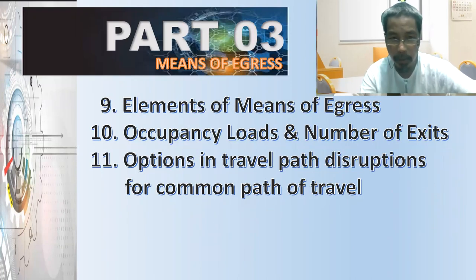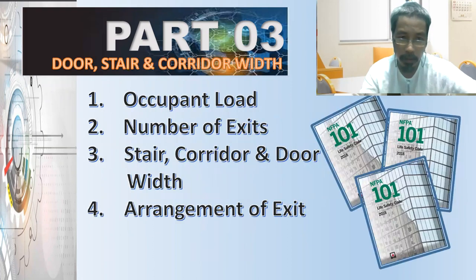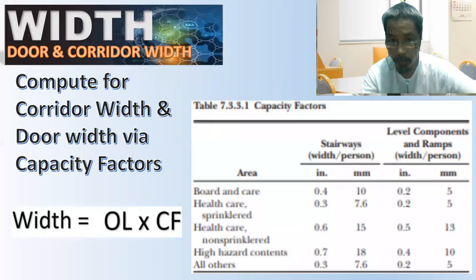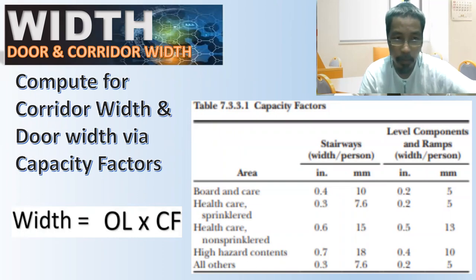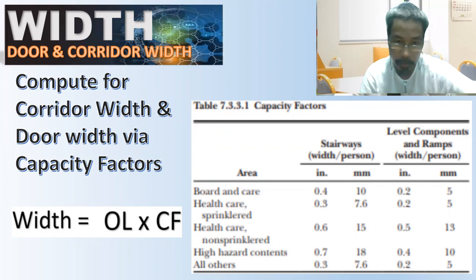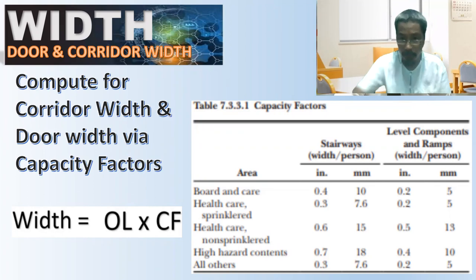Again, there are three major parts. We are currently on Module 10, third part, pertaining to stair corridors and doors. Previously we discussed door and corridor width and how to compute for corridor width and door width using capacity factors. The formula is: width equals occupant load times capacity factor.